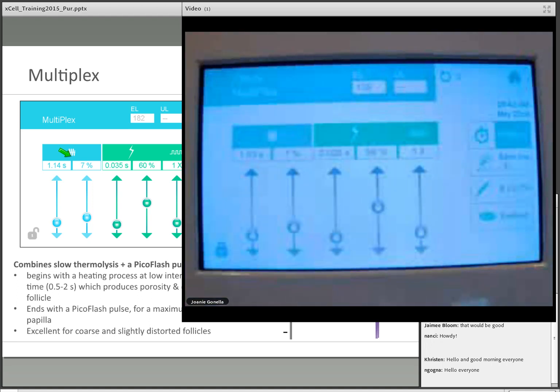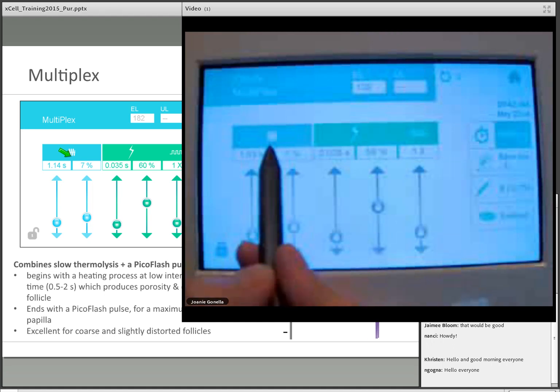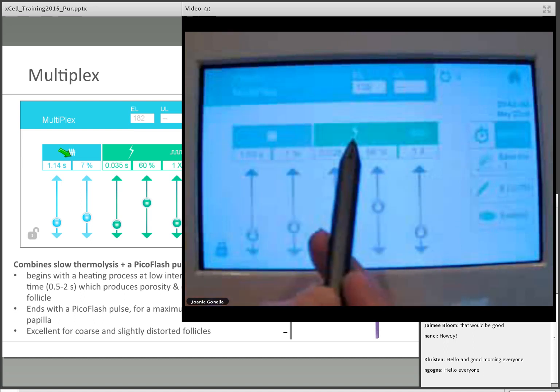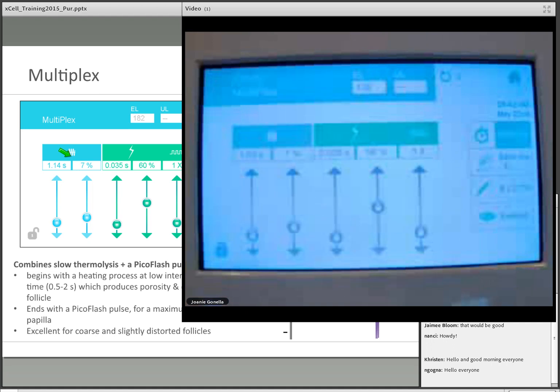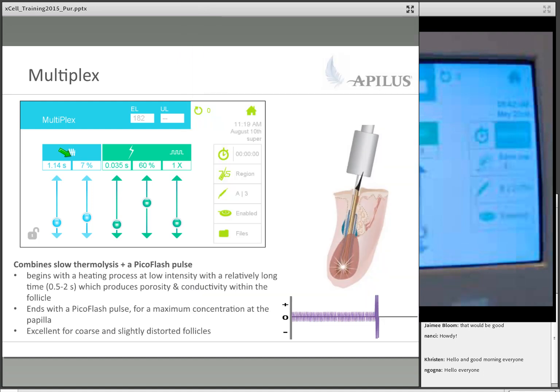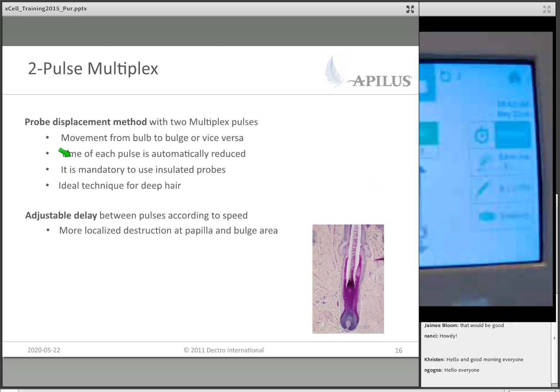this is the noise that I hear. As you can tell, I'm giving it a little bit of very, very low thermolysis, which isn't going to do anything, and no pulse of Picoflash, so no coagulation will happen. So this does absolutely nothing. You have to hold it down and then let it go. If you want to do two pulses with multiplex, it is best set on the machine. Let's go to the slide and I will show you that afterwards too.